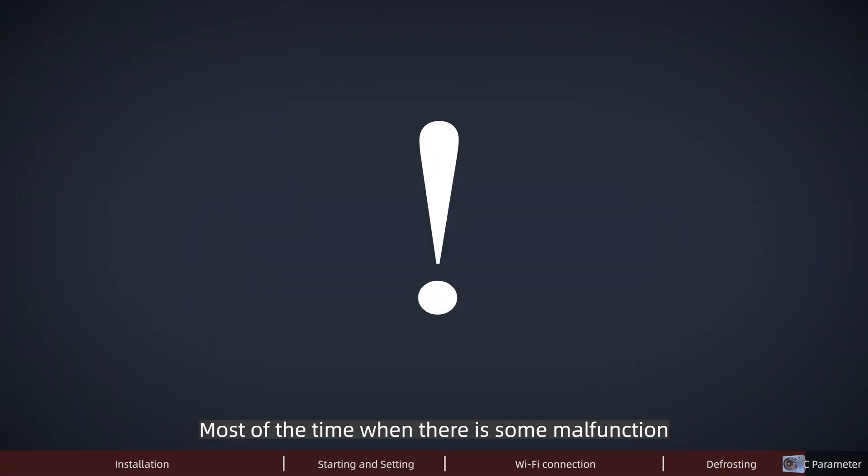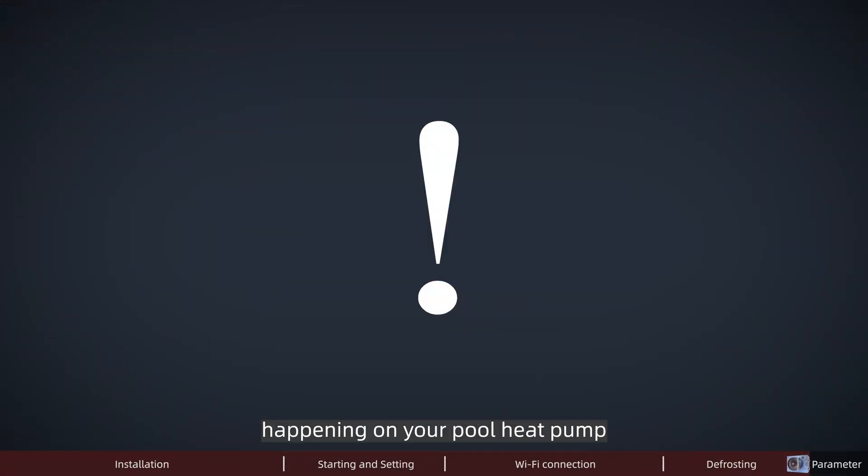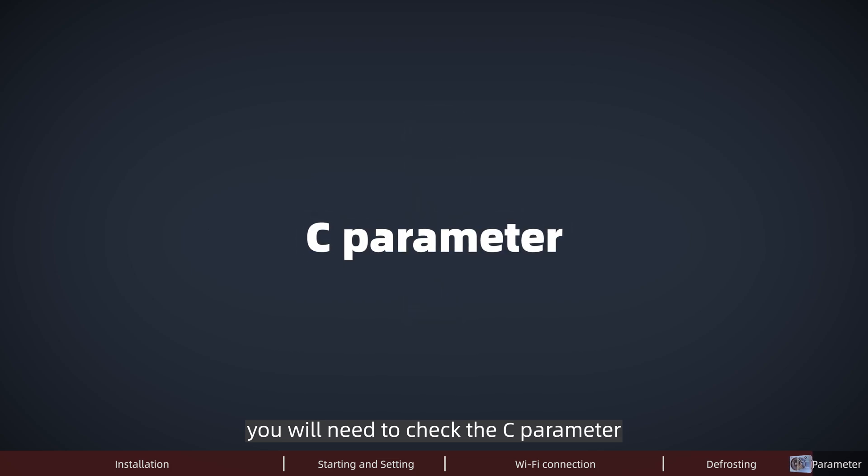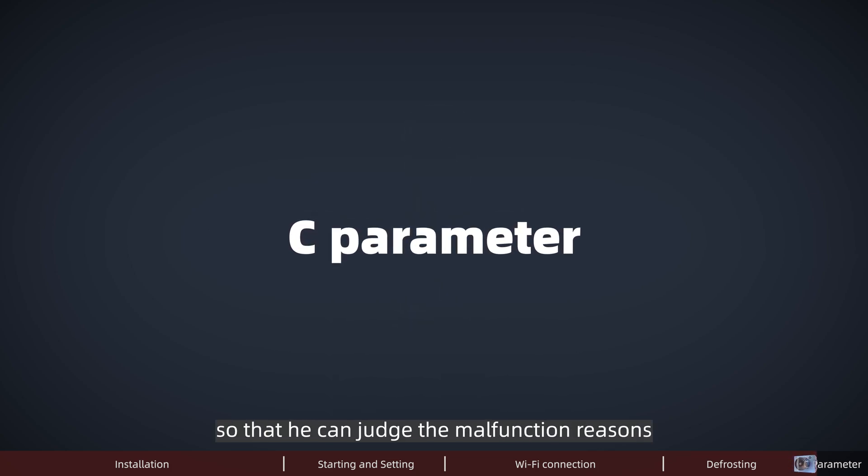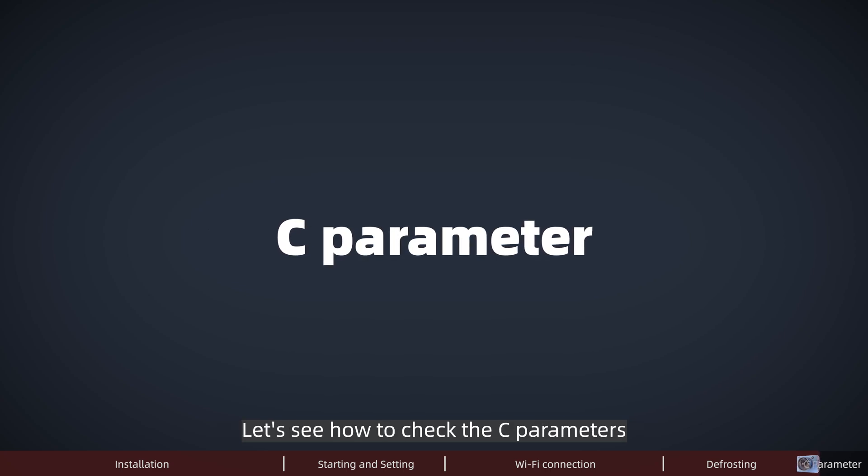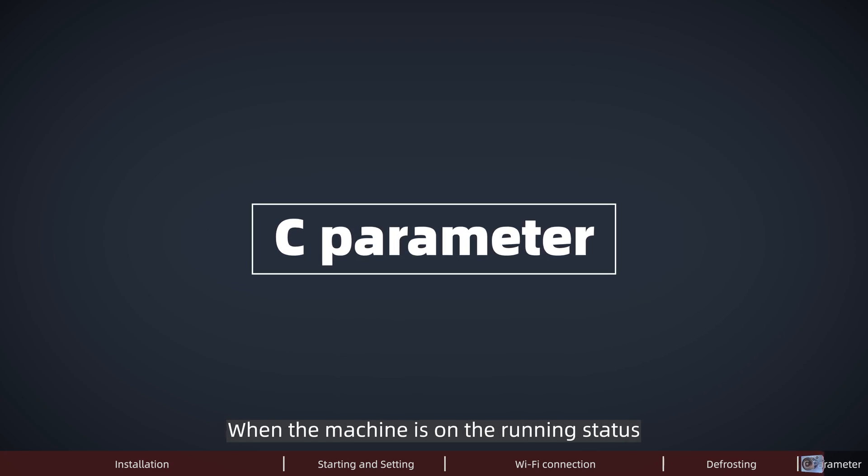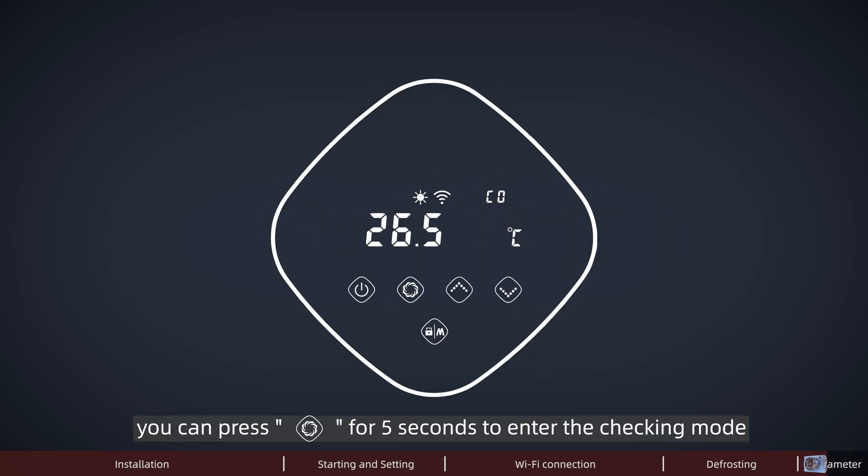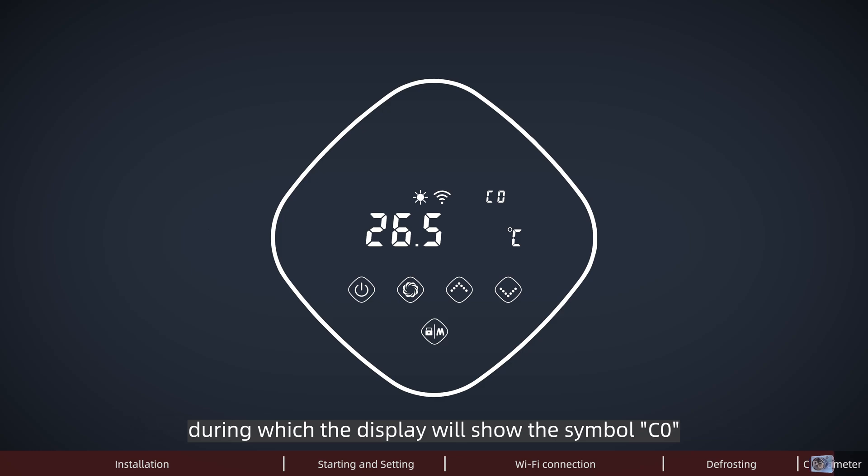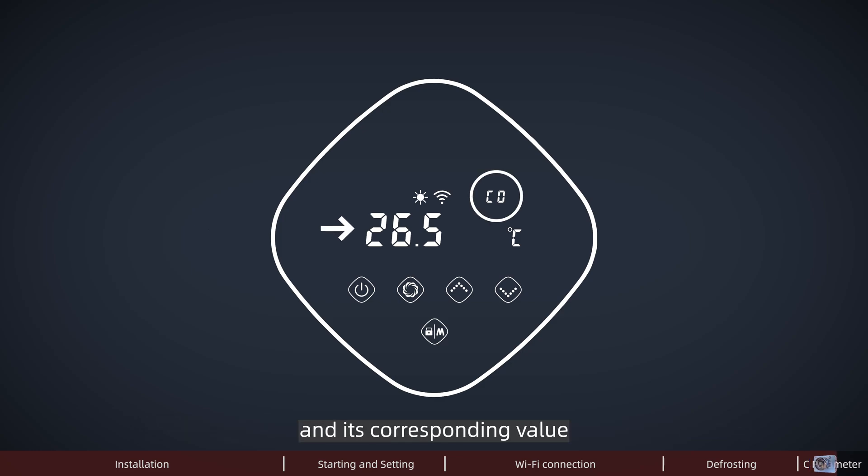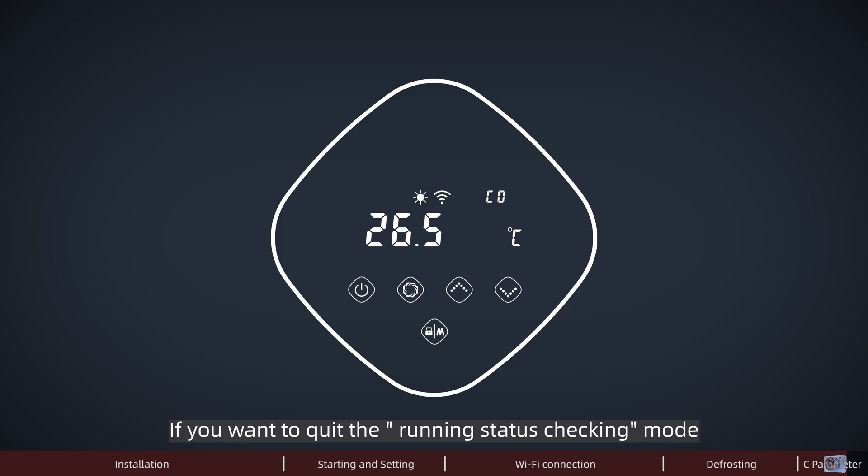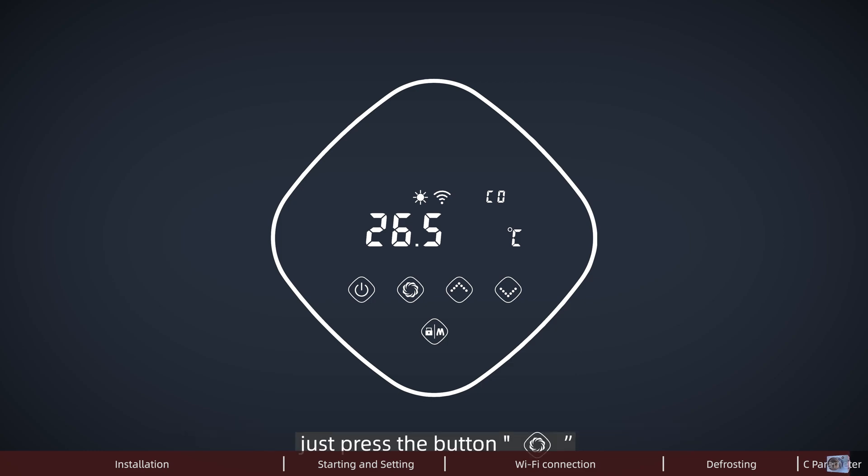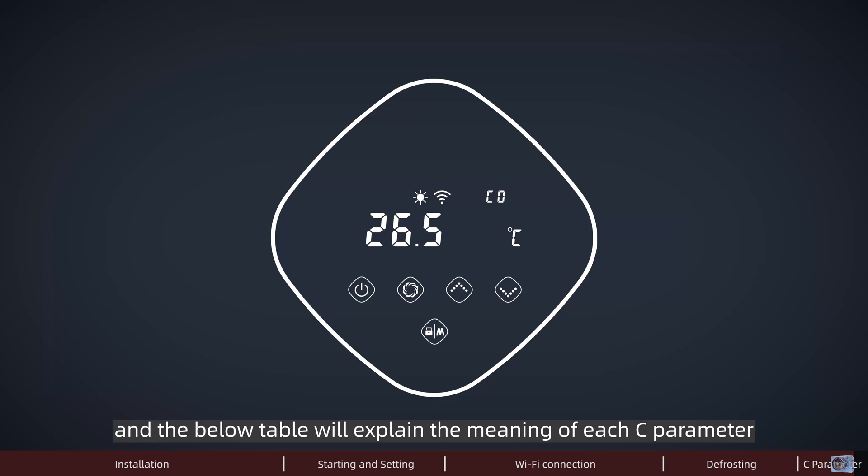Most of the time, when there is some malfunction happening on your pool pump, you will need to check the C parameter and give feedback to the technician so that they can judge the malfunction reasons. Let's see how to check the C parameter. When the machine is on the running status, you can press this sign for 5 seconds to enter the checking mode, during which the display will show the symbol C0 and its corresponding value. You can press the up and down buttons to check different parameters. If you want to exit the running status checking mode, just press this button, and the below table will explain the meaning of each C parameter.